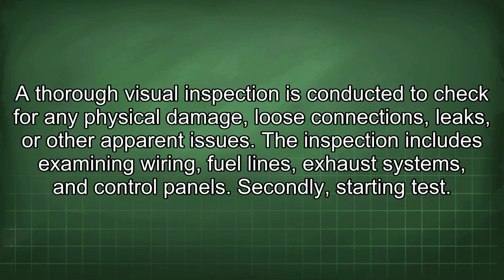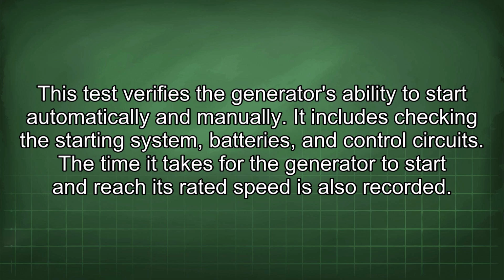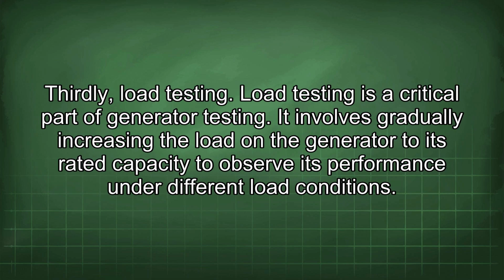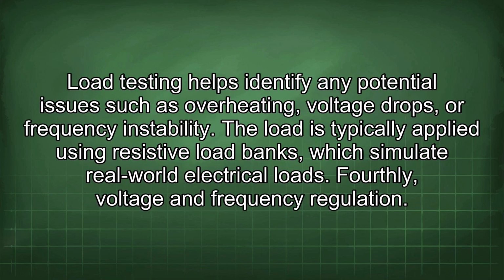Secondly, starting test. This test verifies the generator's ability to start automatically and manually. It includes checking the starting system, batteries, and control circuits. The time it takes for the generator to start and reach its rated speed is also recorded. Thirdly, load testing. Load testing is a critical part of generator testing. It involves gradually increasing the load on the generator to its rated capacity to observe its performance under different load conditions. Load testing helps identify any potential issues such as overheating, voltage drops, or frequency instability. The load is typically applied using resistive load banks, which simulate real-world electrical loads.